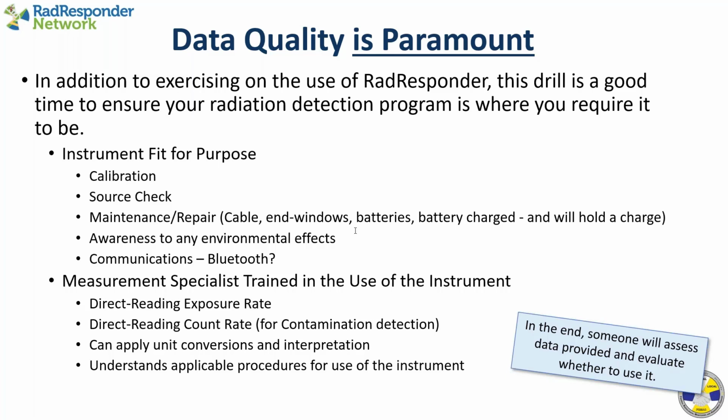Are you aware of any environmental effects with that specific instrument? Does it respond the same? Is the background the same when it's raining, when it's humid, when it is day or night, diurnal effects? Essentially, how familiar are you with your instrument that you're selecting for the background as a function of environmental effects? Because in my experience, for example, you'll get out to the field and discover that the cable you're using has a bad connector if you bend it, and then maybe you've got a problem.